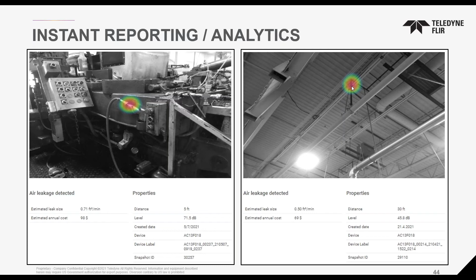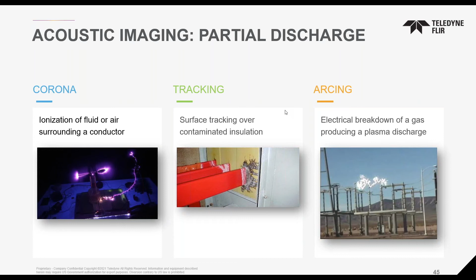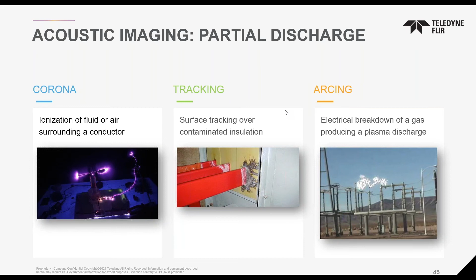Beyond compressed air leaks, our acoustic imaging camera can also detect partial discharge. There are three types: corona, which is the buzzing sound you might hear around a power line; tracking, where energy jumps from the source to another ground and contaminates the insulated area; and arcing, where electricity actually jumps between electrical components, resulting in an arc or arc flash.